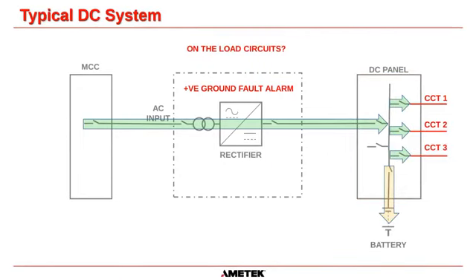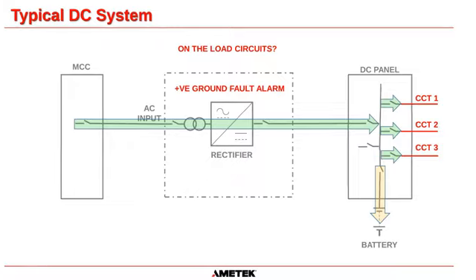That's what this screen is saying. But the problem with that is, in most circumstances, this DC panel may be feeding another 4 or 5 loads. So yes, let's say we open this breaker here, the ground fault clears. Well, we know that it's this branch here that has the problem, but unfortunately there's maybe 5, 6, 7 pieces of equipment that's connected to that circuit. Then we have to go and try and find which individual piece of equipment has the problem. So there are issues with finding faults by just opening breakers.